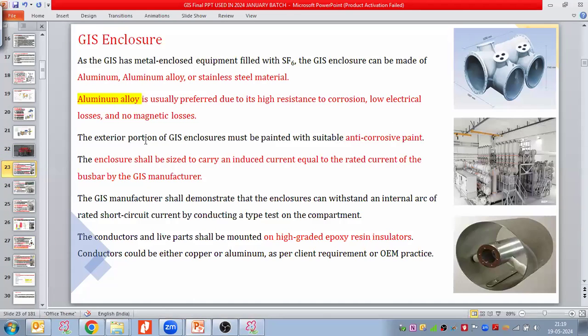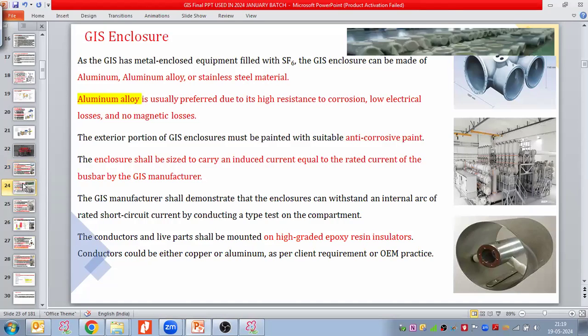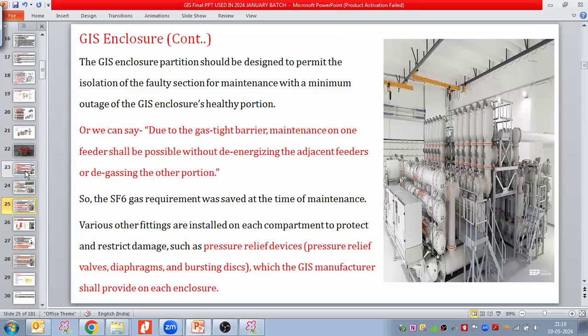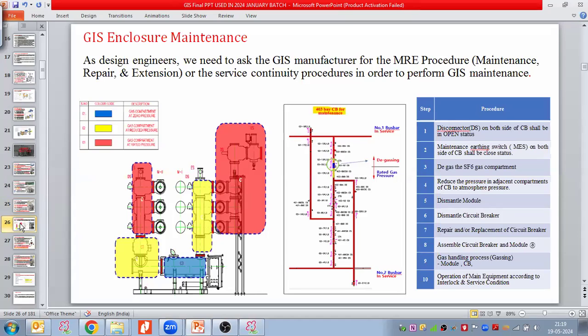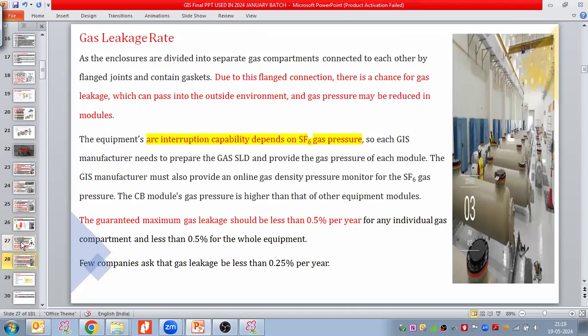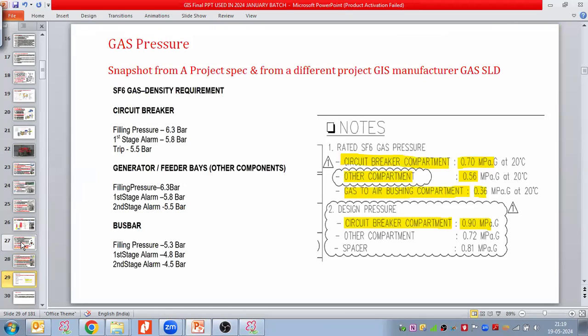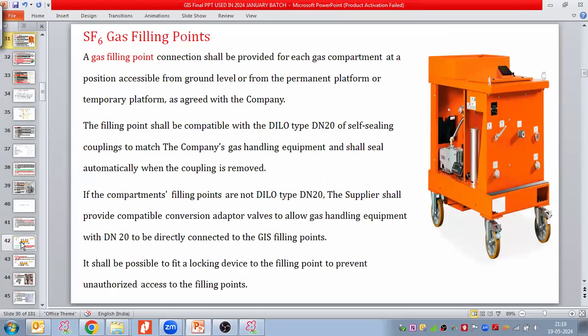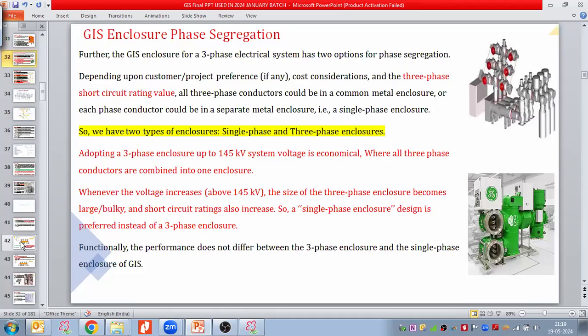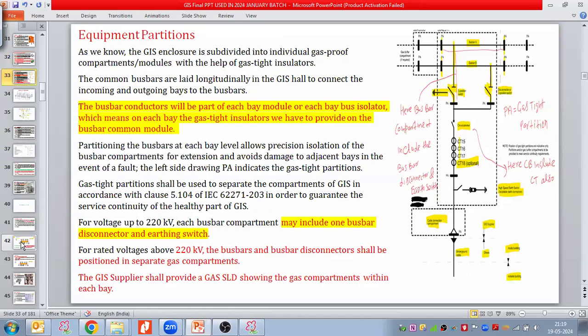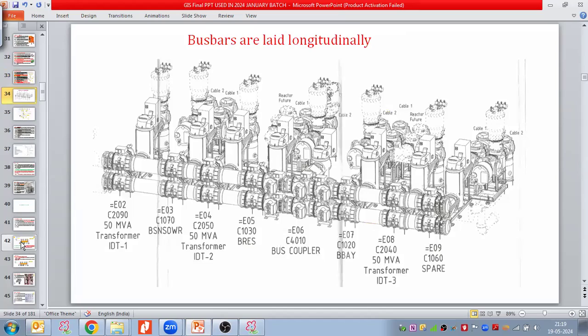So here we discussed the enclosure. We take an aluminum enclosure, and we discussed the enclosures already. Then we discussed the MRE procedure, the enclosure MRE procedure, the maintenance, repair, and extension procedure. That also we discussed yesterday. And then we discussed the gas and gas pressures, gas leakage rate, and gas alarm provided by the supplier. Then we discussed the gas filling point, and then phase segregations. Yes, we discussed phase segregations as well. And then we discussed partitions. That also we discussed yesterday, right?